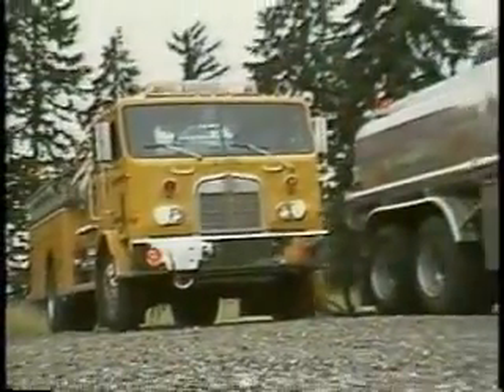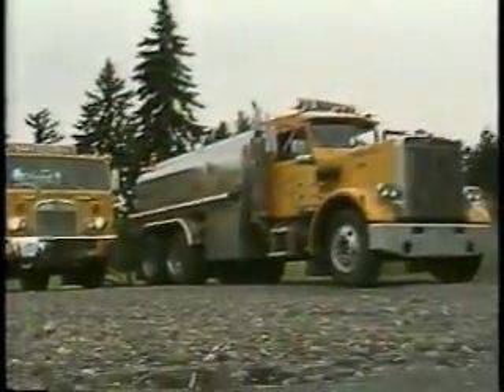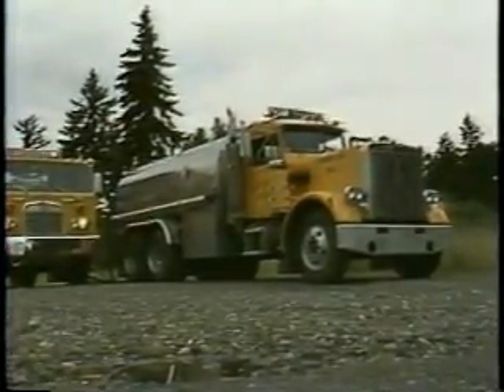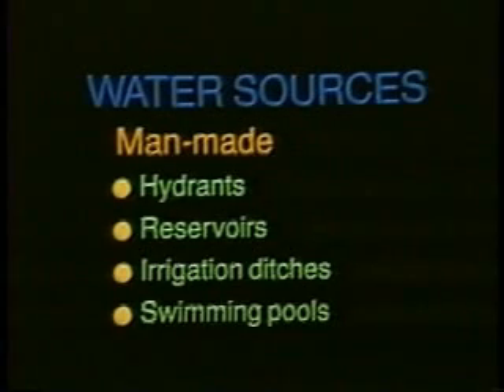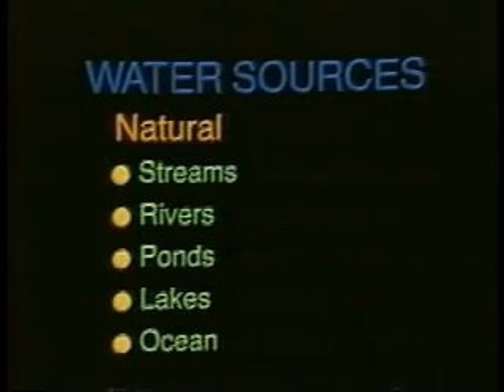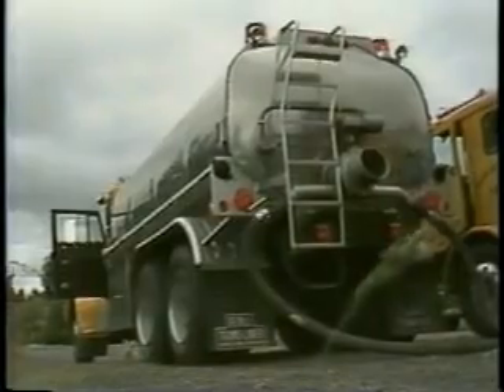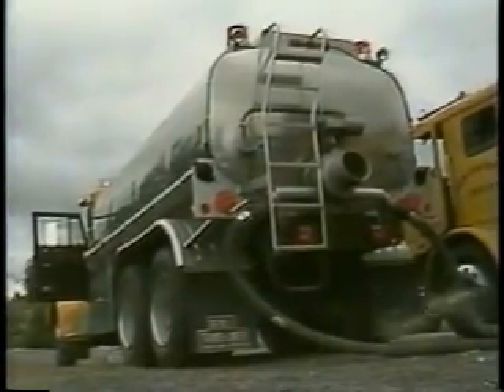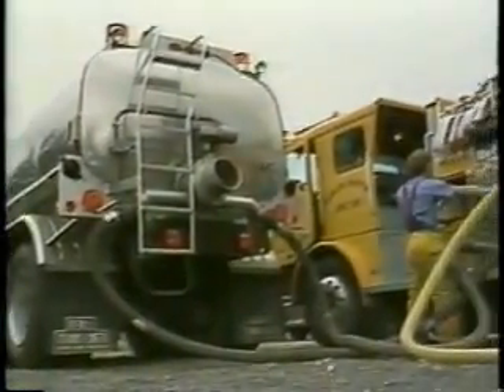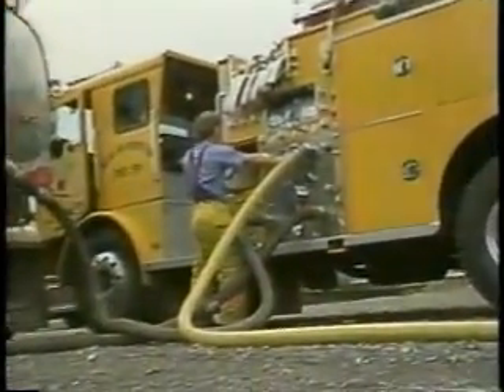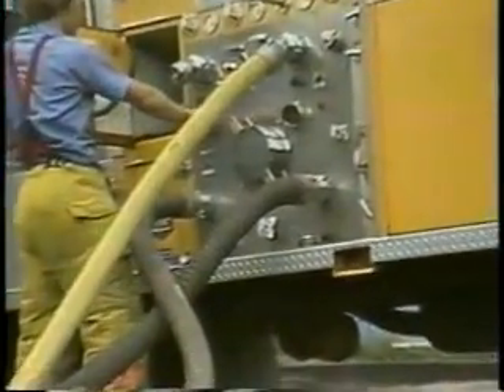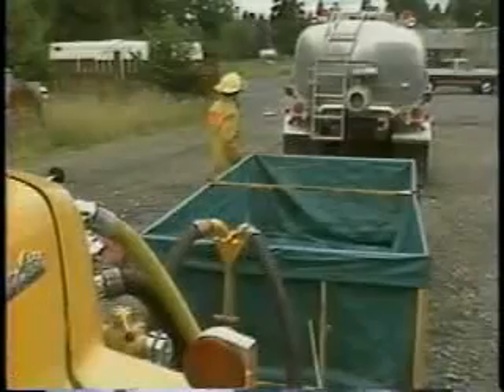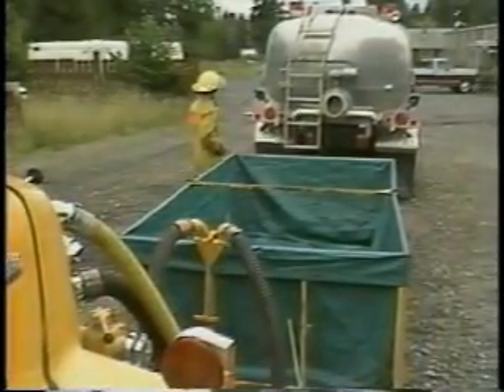In rural areas where hydrants are non-existent, tankers are dispatched with first response apparatus. Tankers can bring water to an apparatus from a distant hydrant or other man-made water source, and from a wide variety of natural water sources. Tankers can feed water directly to a pumper, or drop the water into a portable tank adjacent to the pumper.